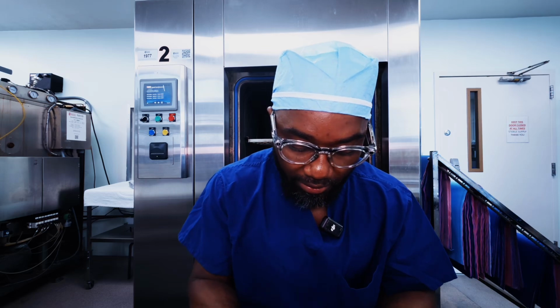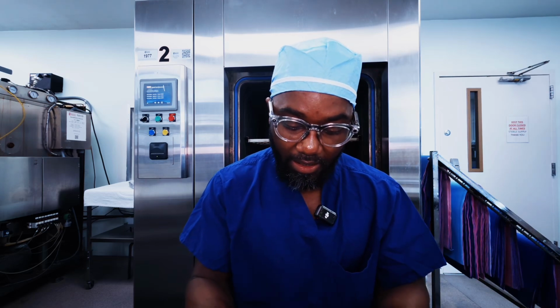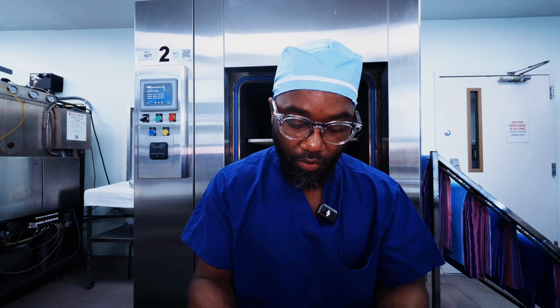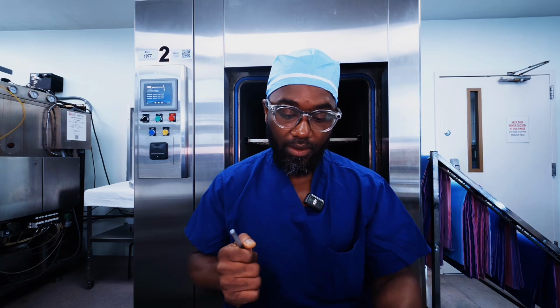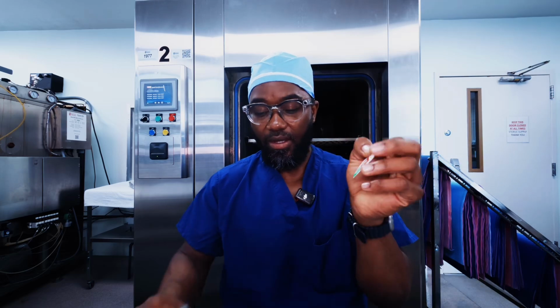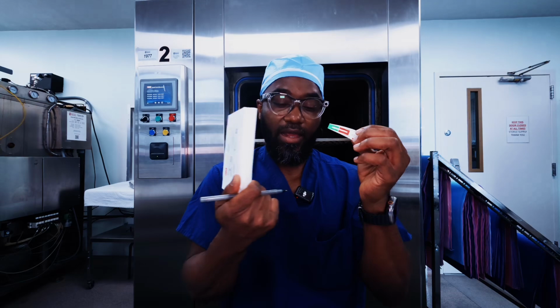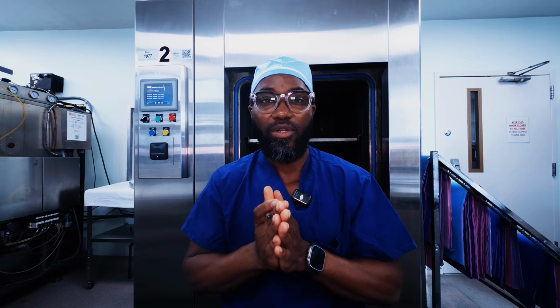and physically check to make sure that we met the 270 degrees Fahrenheit, the minimum temperature, the minimum pressure, and the required minutes that it should be exposed to. If we check our physical printout, our chemical indicator, and our biological test pack, and everything passes, it means that our load in here met the parameters and requirements for sterilization.